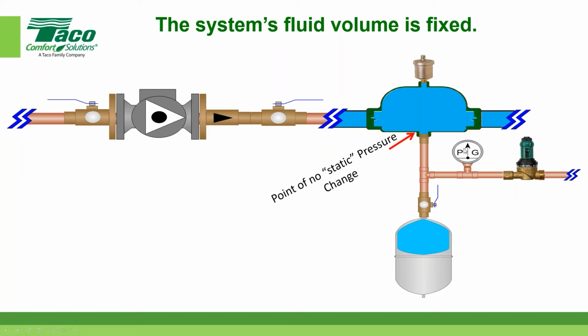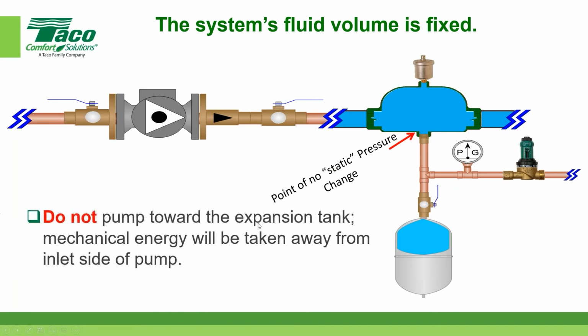So understand what I'm getting at. You have to move that needle, okay? Well, in order to move the needle, you have to have water go down this pipe. If you were to have water go down the pipe, where would the water come from? It's already full. Would you get perpetual more water entering the system from some other location other than where it normally comes in? And the answer is no. So it doesn't matter how big this pump is, you're not going to move that gauge, okay, in this scenario that I'm showing you now.